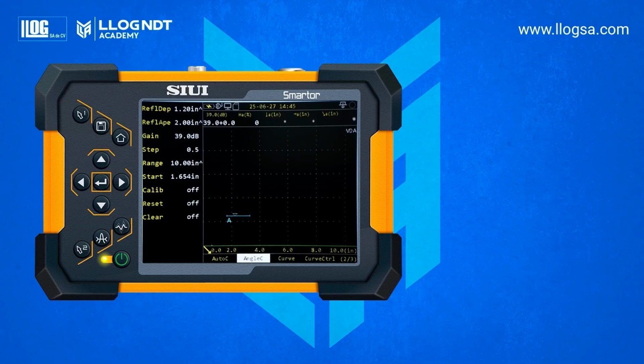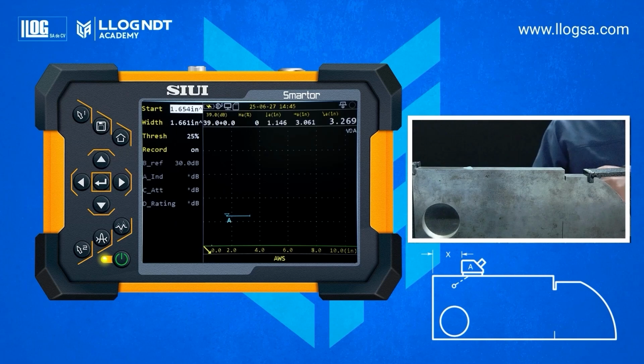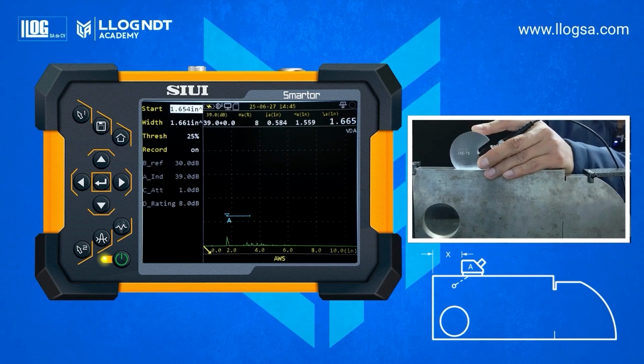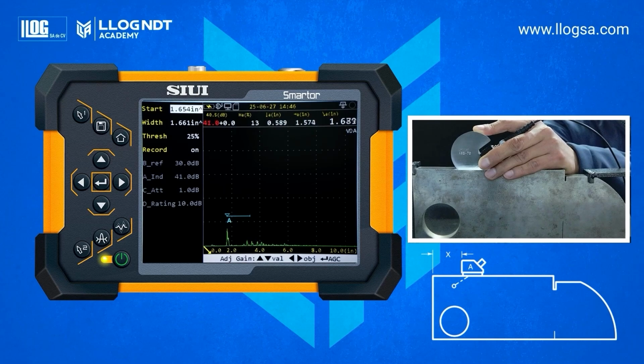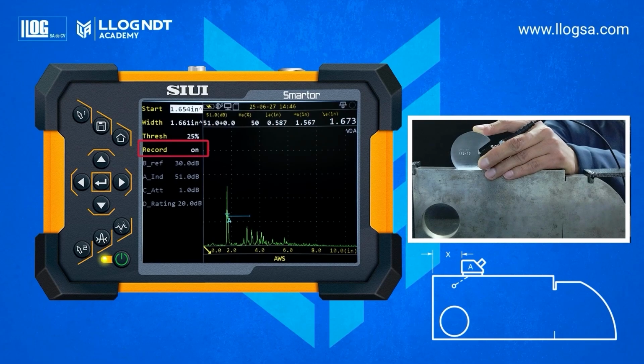We will now continue with the sensitivity adjustment from the AWS menu. Place the transducer in position A. Move it back and forth until you obtain the maximum echo amplitude corresponding to the 0.6-inch diameter hole. Once the maximum amplitude is found, adjust the decibels, either increasing or decreasing, to bring the reference echo amplitude between 40 and 60%. In this case, we adjust the decibels to set the height to 50%. Press Enter on the record function to store the sensitivity setting.